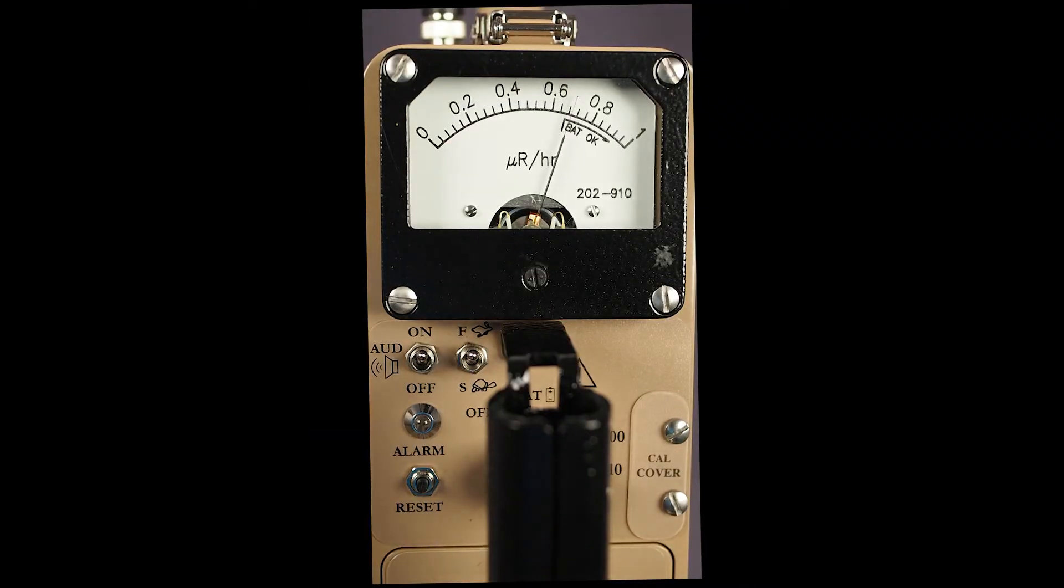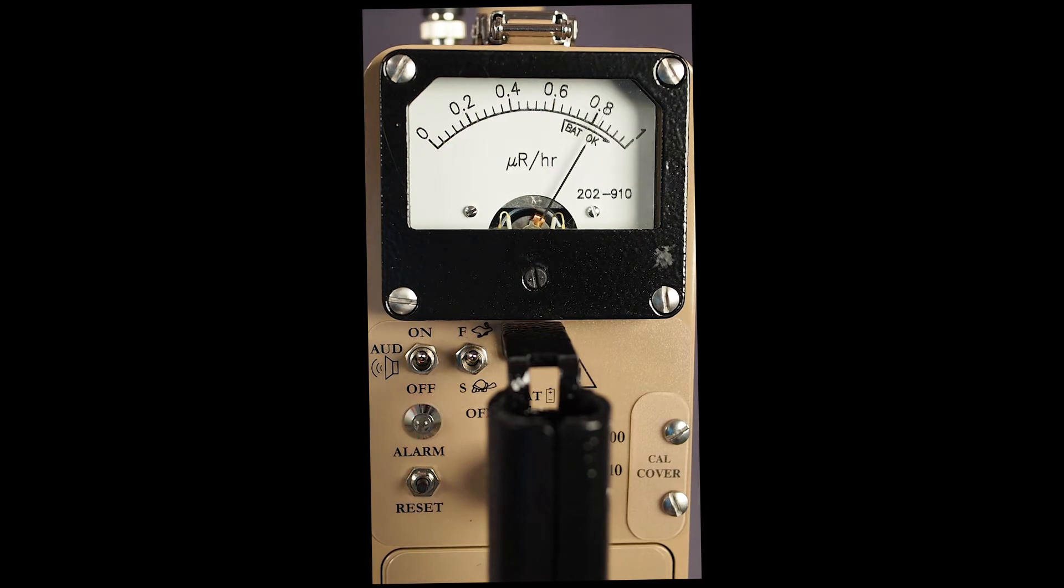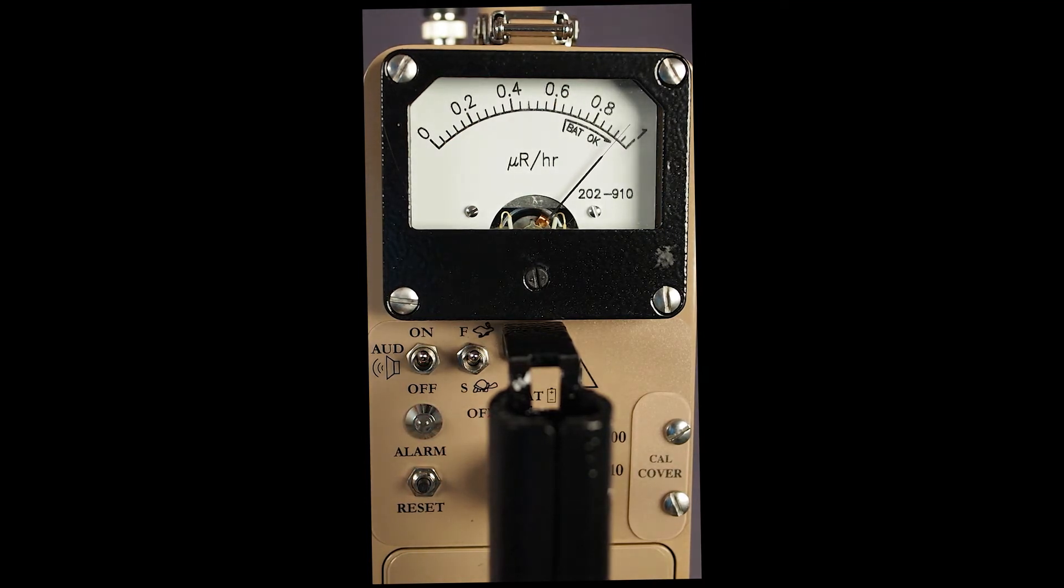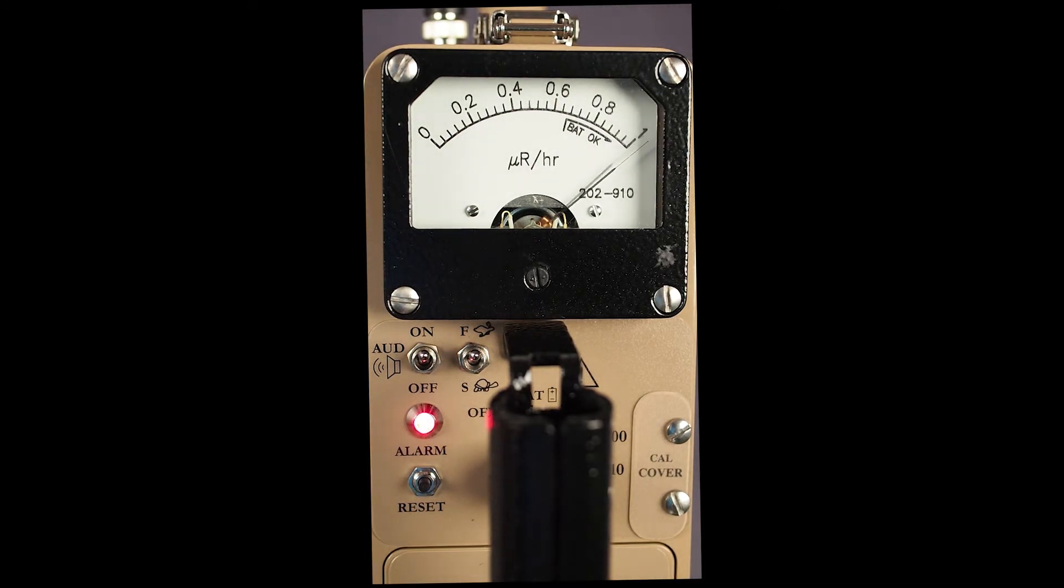The alarm light flashes when radiation levels rise above background. When the meter pointer deflects above the fixed alarm setpoint, this red lamp illuminates continuously. In both cases, the visual alarms will be accompanied by an audible alarm.